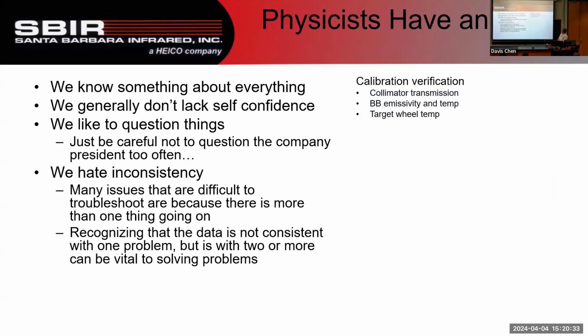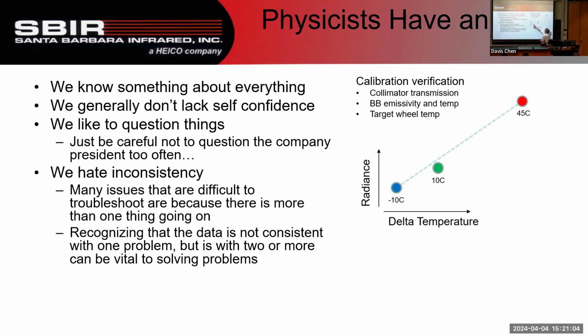As a quick example, recently we had to do calibration verification of a target projector. It's a collimator. Basically, it's a target projector, like a collimator with a target and a source. So there are 4 things that matter, right? The collimator transmission, the blackbody emissivity, the blackbody temperature, and the target temperature. Those are the 4 things that you need to do the calibration. So the guys run their calibration verification test, and what do you know? It matches at -10, it matches at 45, fails at 10.